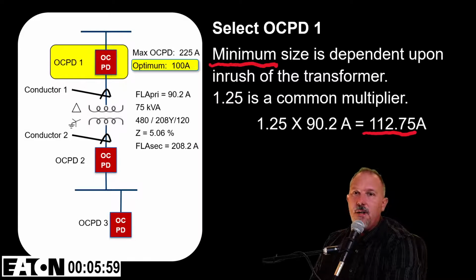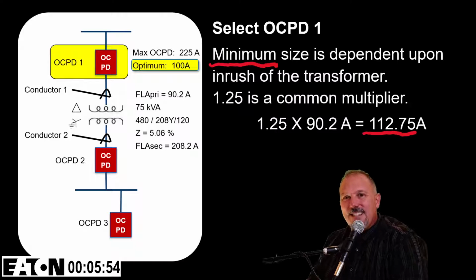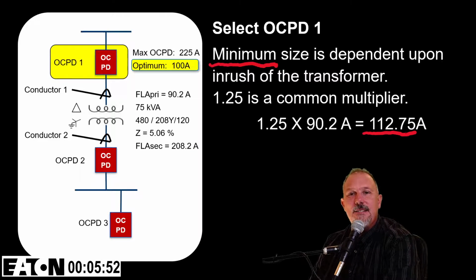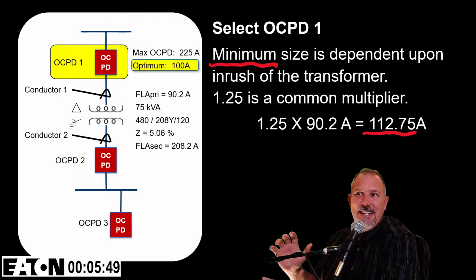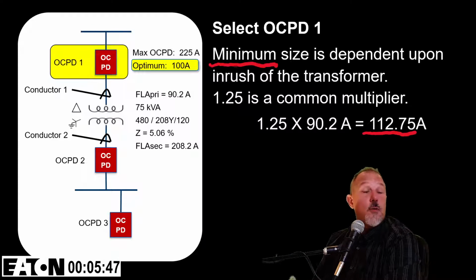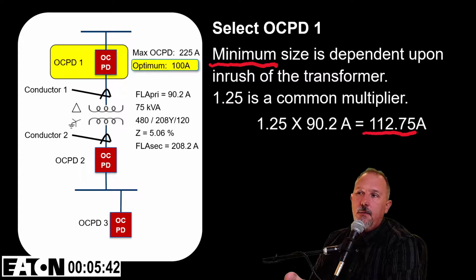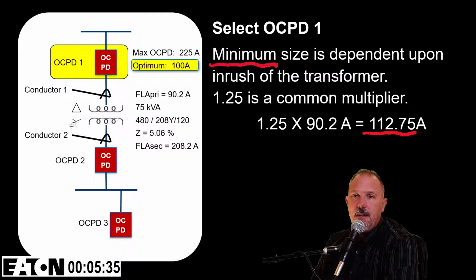Now, I've talked to a couple engineers. I had some good discussions with one person. It was a heated debate with another individual, very logical, as a matter of fact. The one design engineer that I talked to said you would typically see about 110 amps on the primary of this device. They would definitely not go to 225 in a normal application, but you'd probably see about 110 amps on the primary.